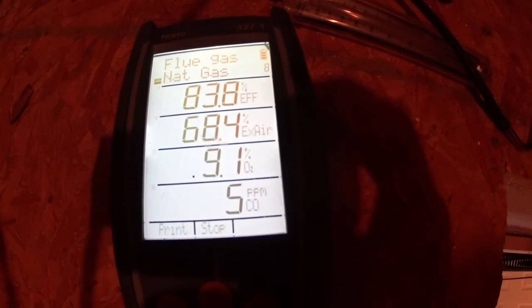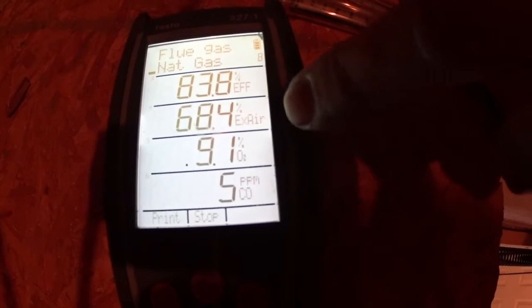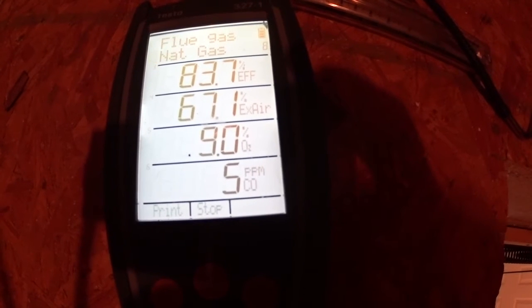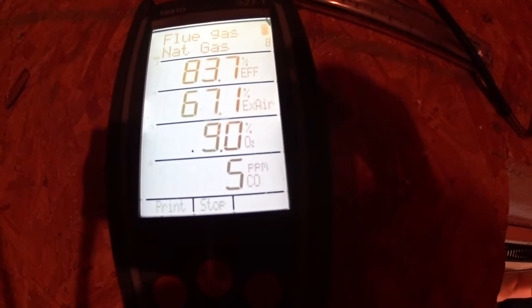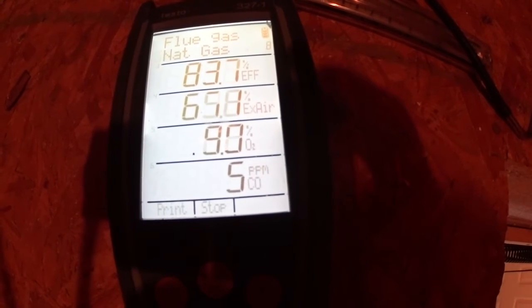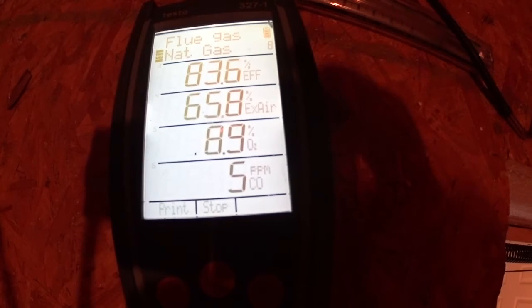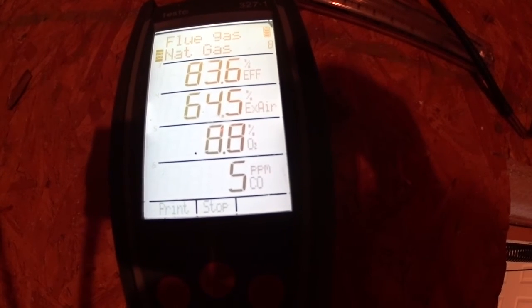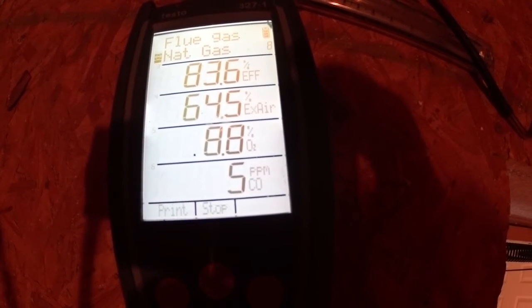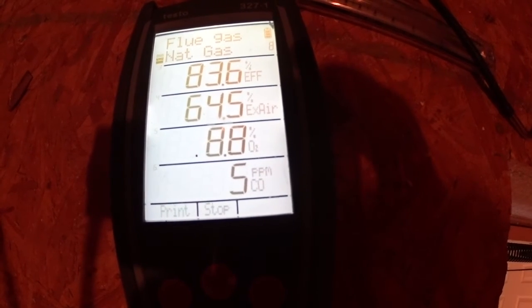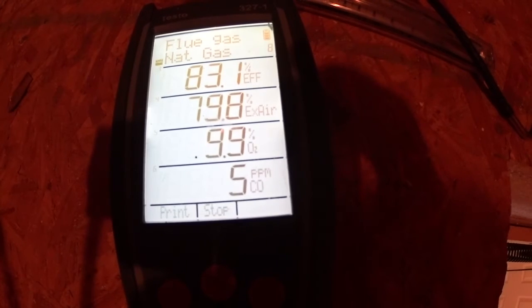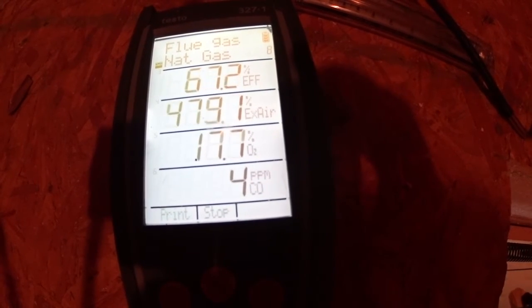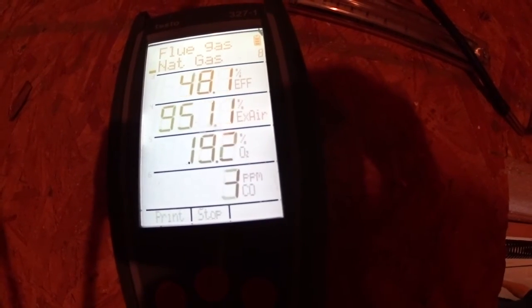Let's cut it off — turn it off from the thermostat. Watch that number — parts per million — make sure it doesn't rise. Parts per million stays solid, it's going to be a little drop, it will not rise. It stayed steady for a while and dropped to 4, 3.